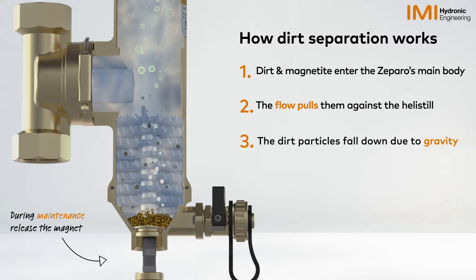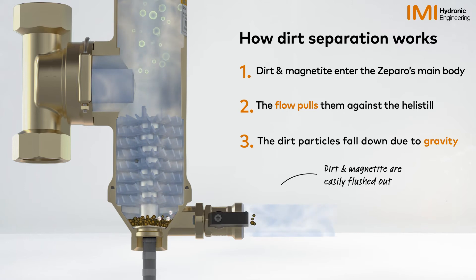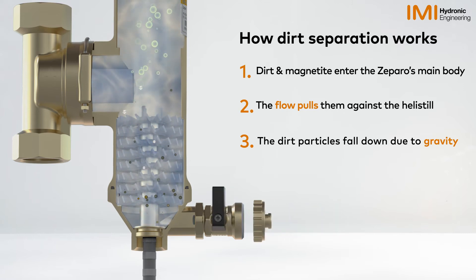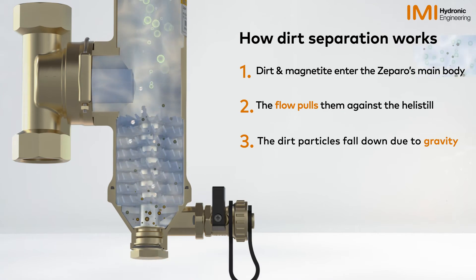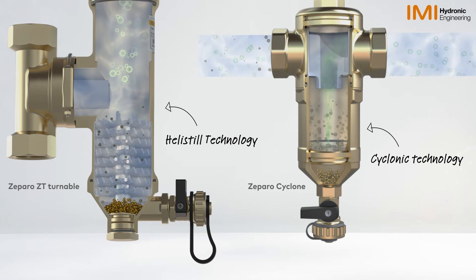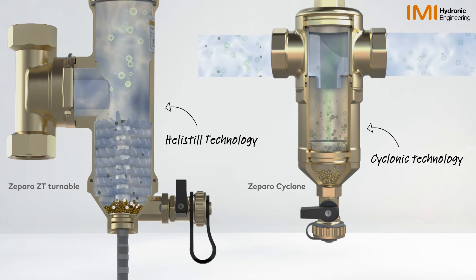During maintenance, the magnet has to be released before opening the shuttle valve so that the magnetite can be flushed together with the collected dirt. IMI Hydronic Engineering has long experience in the most efficient technologies for dirt separation: Helistill and cyclonic.